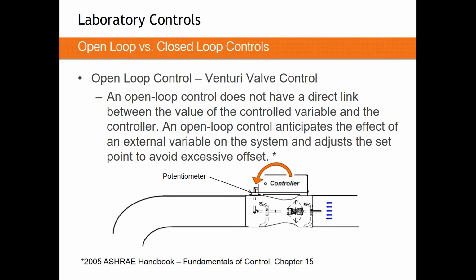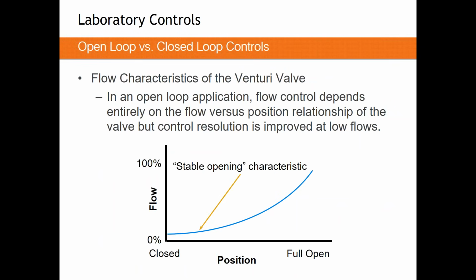Now, the great thing about these, number one, is that they're not naturally shut-off devices, but also, because there's no measurement happening in between and there's no resolution to deal with, there's a stable opening characteristic. So from minimum flow to maximum, you get a nice, clean, fairly linear, stable opening on a Venturi valve, which gives us that huge turn-down ratio of 20:1 in some Venturi valves in the medium pressure variety. So this is really nice if you're dealing with fume hoods or even low flow applications.